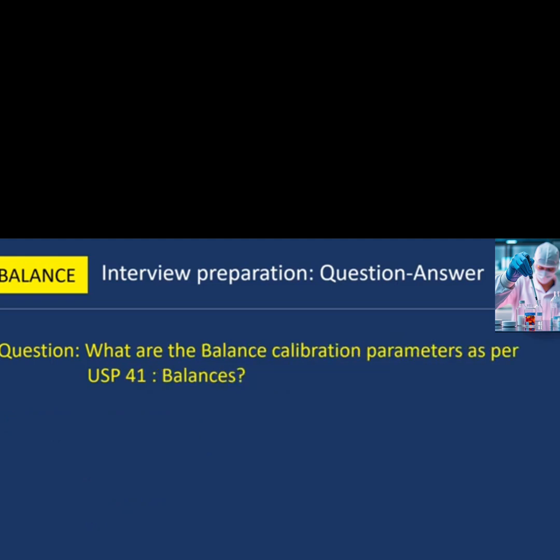Next question: what are the balance calibration parameters as per USP 41 Balances? The balance calibration parameters as per USP 41 are: first, repeatability; second, accuracy.